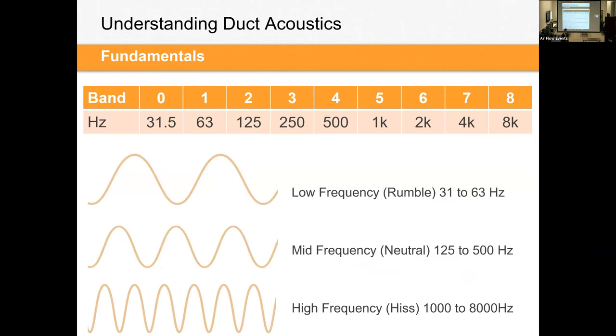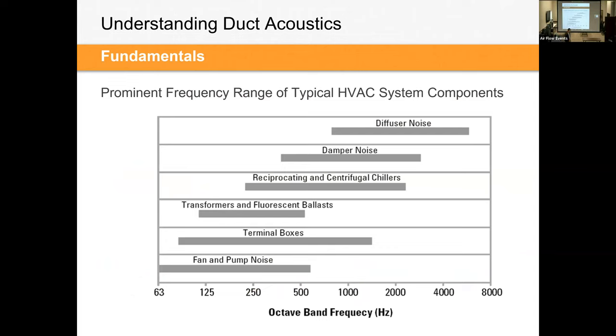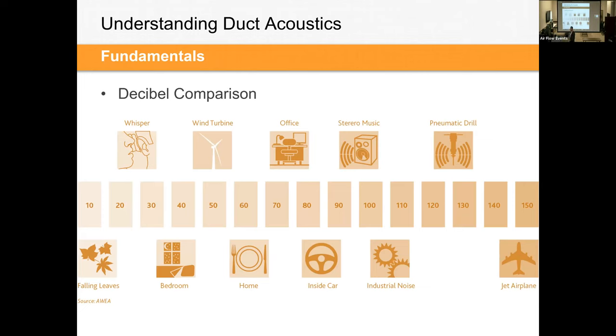Different HVAC components produce different frequency ranges. Fans and pumps are typically low frequency — a vibrational, bass-like rumble. Diffusers and dampers produce higher frequency noise — more of a hiss from high-velocity air. Understanding this helps diagnose noise problems: low-frequency rumble suggests a fan or pump; high-frequency hiss points to a diffuser or damper.